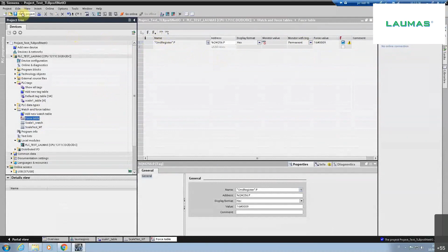Now we can save the project, and before going on, we can focus for a moment on the physical device. More precisely, in order to obtain a correct communication between the PLC and the TLB, it is mandatory that the name of the physical instrument in our Profinet network is equal to the name assigned to it into our TIA portal project. In this case, this means that our physical TLB has to be named as scale 1.